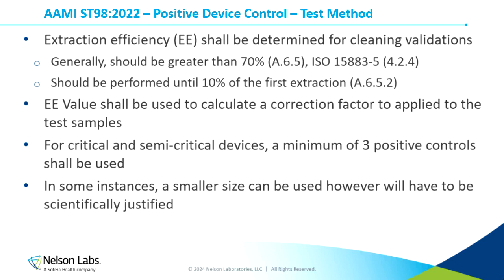So talking about the positive device control, ST98 states that extraction efficiency shall be determined for cleaning validations. And there is now a recommendation for the criteria surrounding that extraction efficiency, that it should be greater than 70%. That is also outlined in ISO 15883-5. We typically perform 4 extractions on the positive device control, and that should be performed until 10% of that first extraction is remaining.